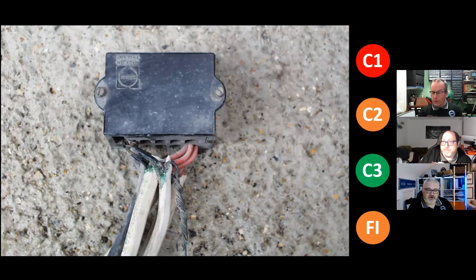There's signs of, the earthing arrangement is horrific. There's signs of chemical breakdown on the insulation, because of all that green goo. The neutral looks like it's burnt out. It does look like it's not quite home in there, doesn't it? It looks like it's just given up the ghost. That's definitely not on an RCD.